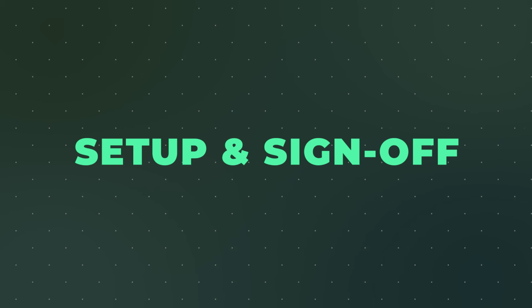So we've gone through the process. What we know is we've got to apply for permission in advance. We then will get an offer letter, and we may well have to do what's called a G100 limit, which is where we limit the export rate going out. But there's also a process afterwards. We then have to write back to the DNO again, on this waiting hold music, and again you can be in for another 30 to 45 days after installation, and we eventually have to tell them, look, this is what we've actually installed, thank you very much, we've limited the export, we've done all that hard work.